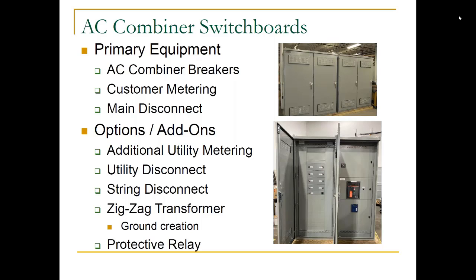Different options, you can add additional sections if utilities require metering within that AC combiner switchboard. You could have another metering. We've seen as many as 3 metering compartments on some of these installations, a customer metering compartment, a utility metering between the AC combiner smaller circuit breakers and the main breaker, and we've seen one then between the main breaker out to the actual transformer connection. You might have a zigzag transformer connection to do a ground creation and do any protective ground fault tripping on the AC board. And certainly an option for a protective relay, if that protective relay is going to be what opens up the main breaker disconnect if there's a fault condition that's detected.